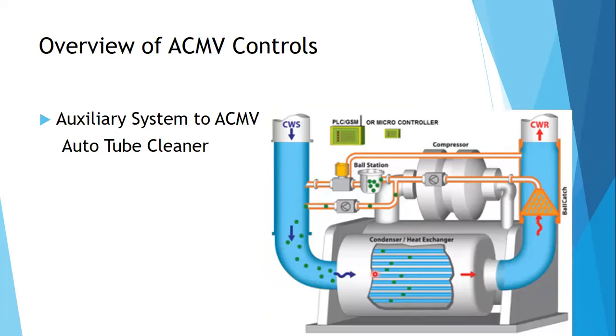Another one is your auto tube cleaning system, or auto tube cleaner, for your chillers. These auto tube cleaners are small balls that go inside the tubes of your chiller. When the balls and the tubes come in contact, frictional force helps scratch the linings of your chiller tubes, and the balls are recycled, making your chiller clean for a much longer time, so the maintenance period becomes much longer, with lower frequency.